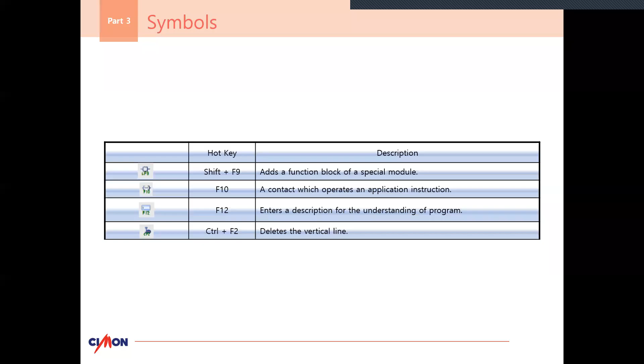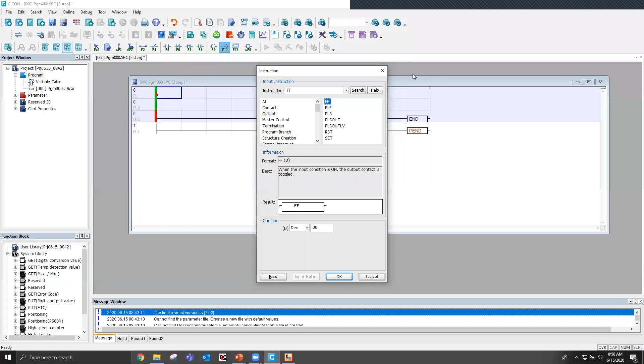In the top part, we have a normally open contact, meaning examine if closed - if this becomes a 1, it will commit to the right side. So when F90 becomes 1, Y20 over here will also become 1, it will become energized - we call this an energized output. Also, since it's on the same rung, row 4, it will also commit to the double word move. D-move stands for double word move, meaning it will take D0 and D1 and move them respectively into D10 and D11. I'll show that on the memory monitor real quick.